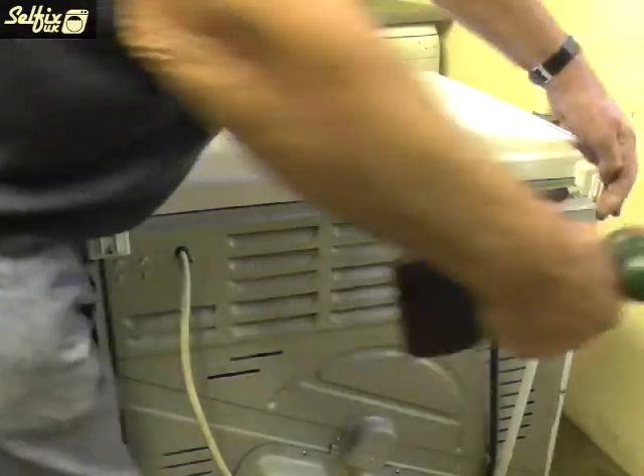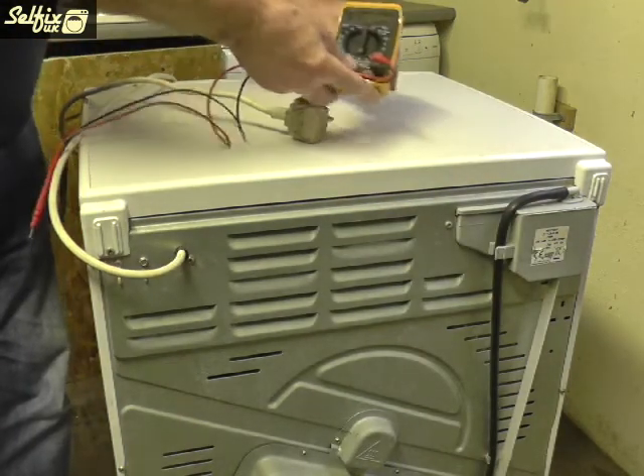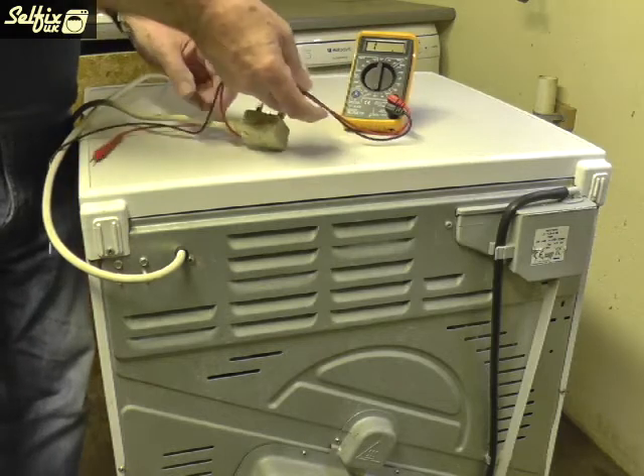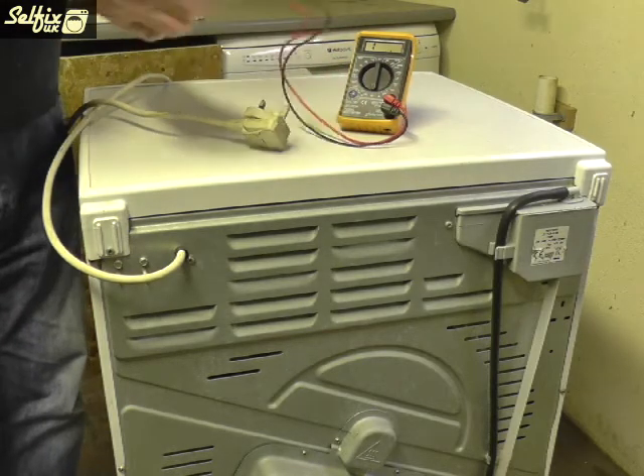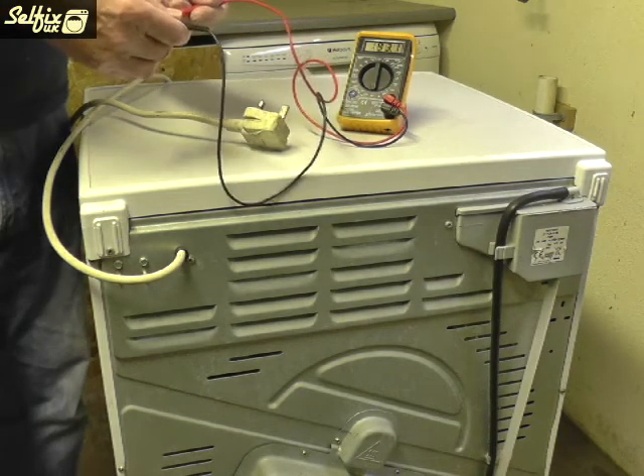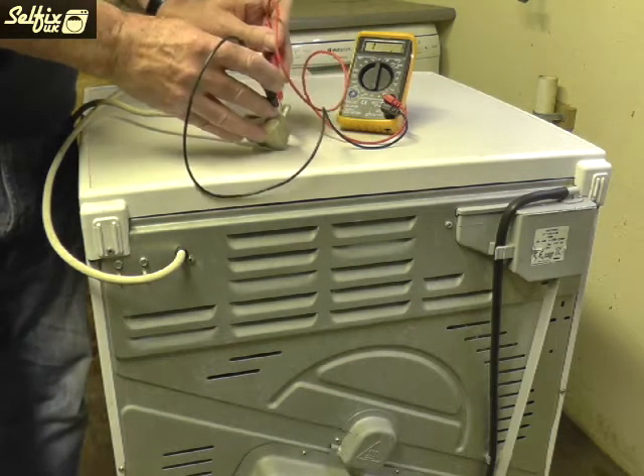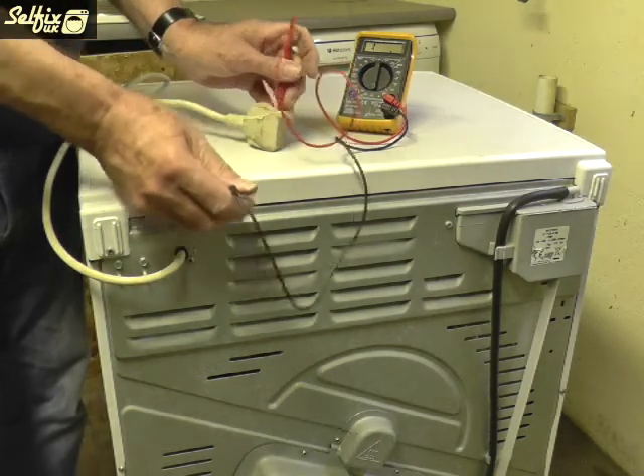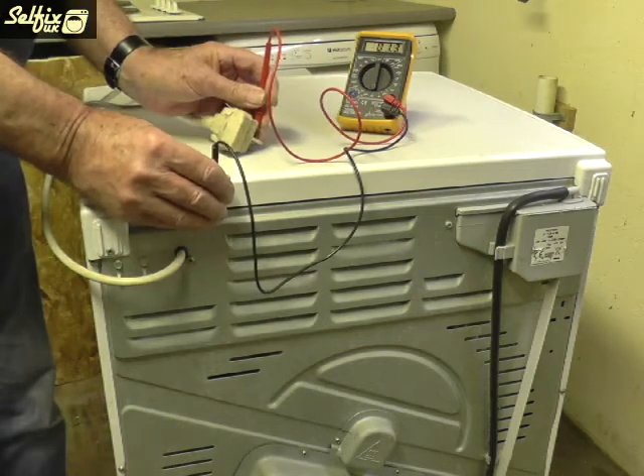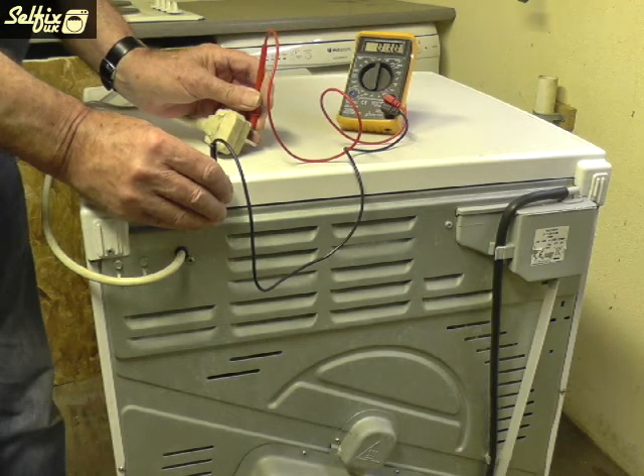But before you connect it up, take a minute to do an earth continuity test. Set the dial to 200 and attach one probe to the earth on the mains plug, whilst touching any exposed part of the cabinet with the other probe. You should get a reading of about 0.5 ohms, but as long as you get a reading then you should be fine. However, if there is no reading, you may want to take another look at the machine because you've got no earth.